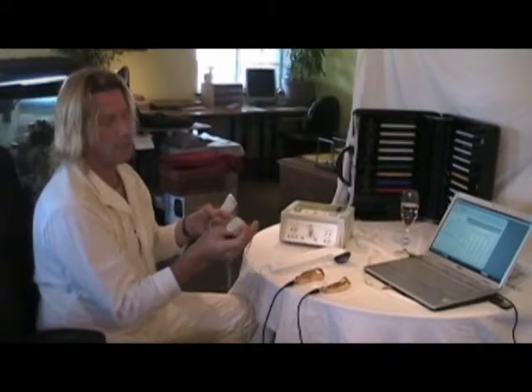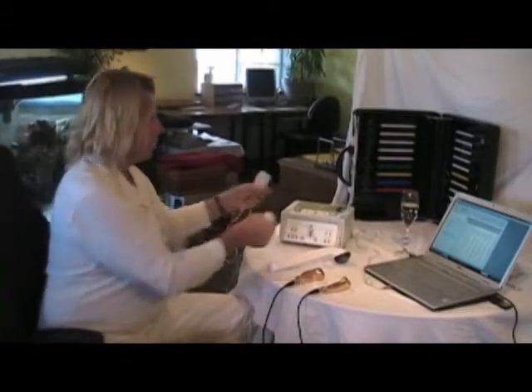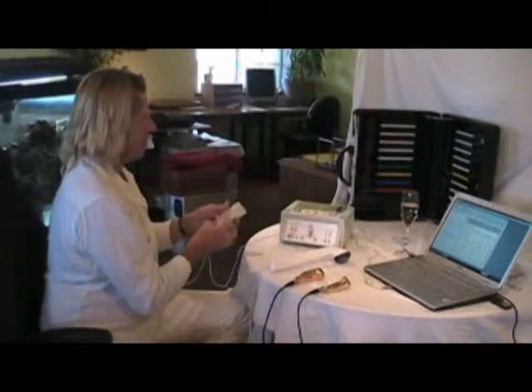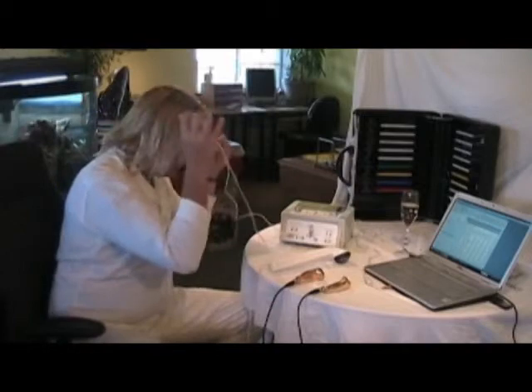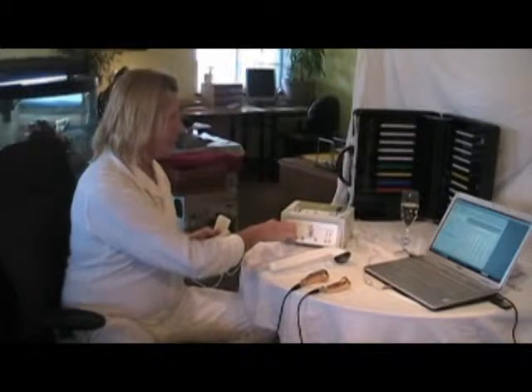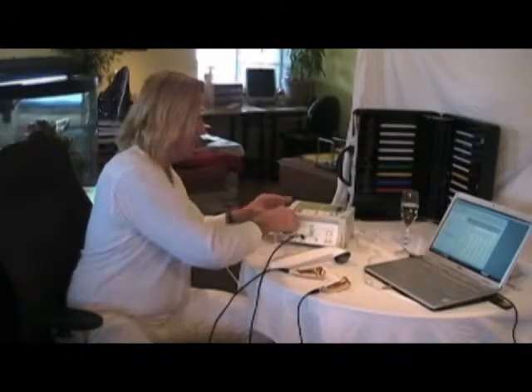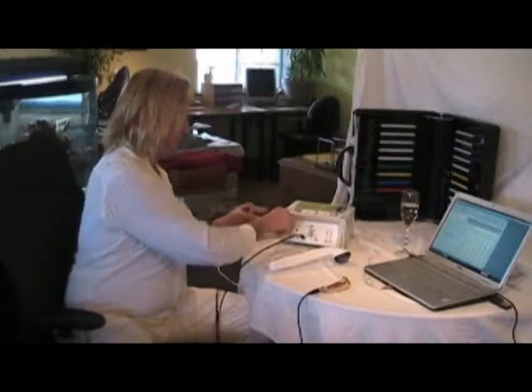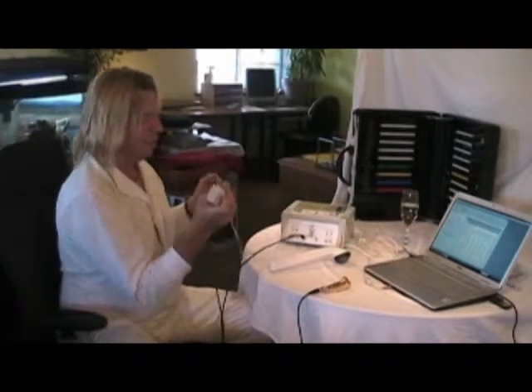With the hair applicator — which you can also use for animals — the electrodes go through the hair. You put one electrode in the signal and the other in the reference. They also have extension cords, so you can place one here and the other in different parts of the body. You always need to have one electrode in the reference and the other in the signal or channel. That's the whole idea.